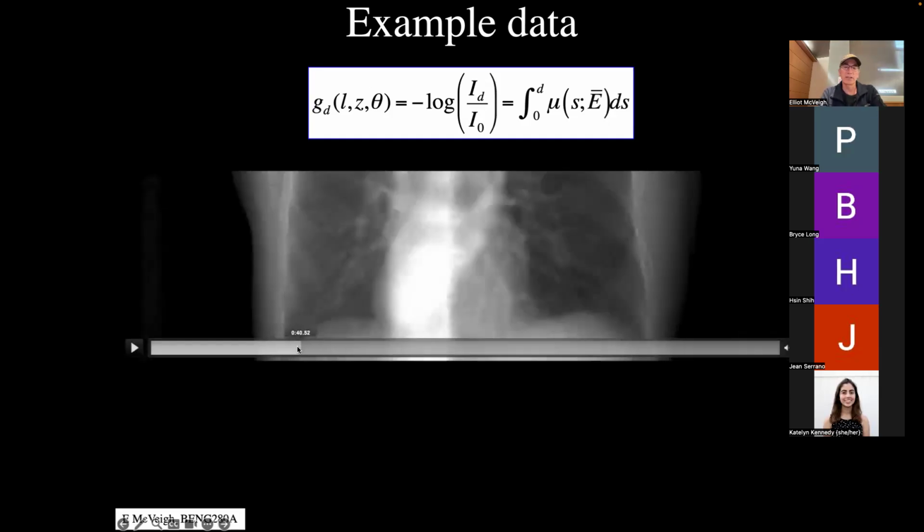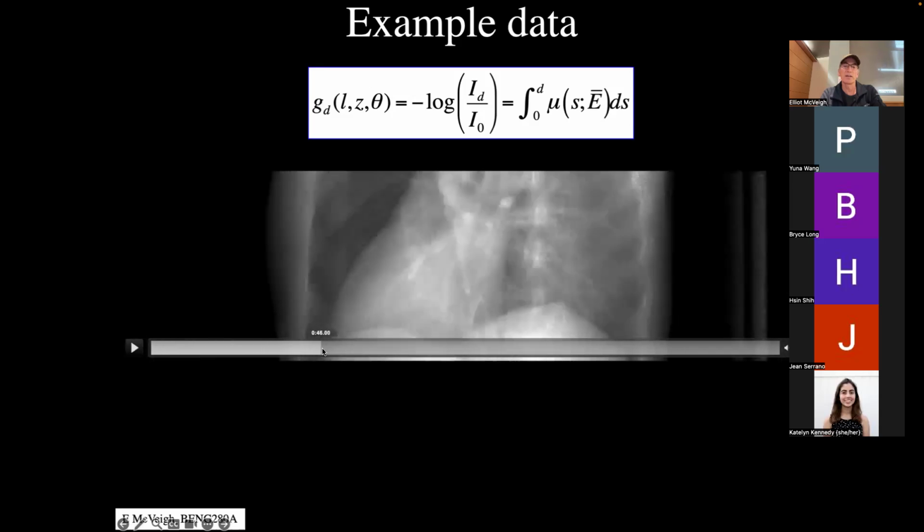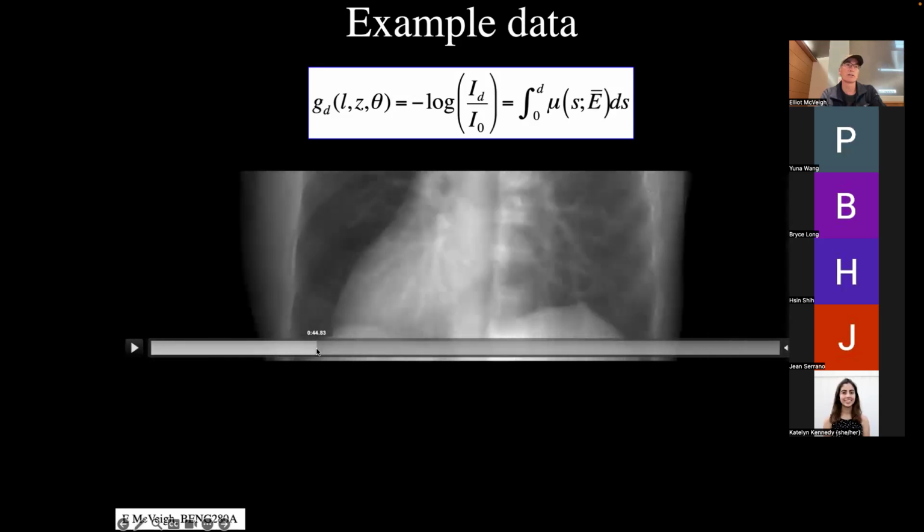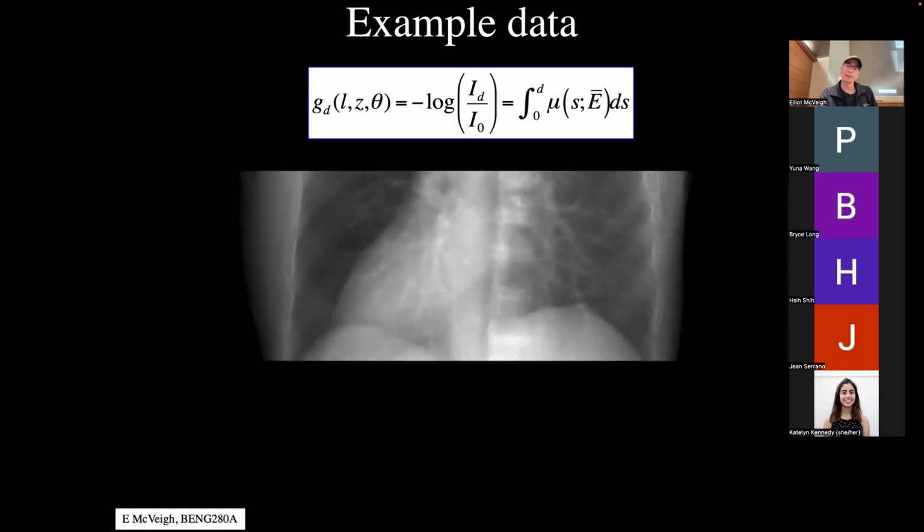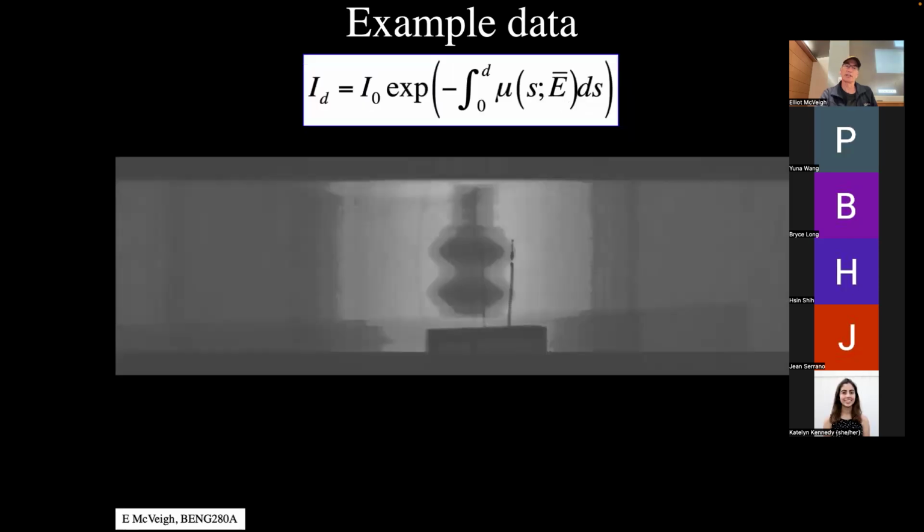That is a great question. And my answer to that question is I believe it has undergone all those corrections. Because normally when you take raw data off your scanner, if you're inclined to hack into machines and grab raw data, you're going to get something like this, right? And it hasn't gone through all of their processing, and they're not going to tell you how they do that, right? And the reason they don't tell you is because they make corrections for shortcomings in the machine.